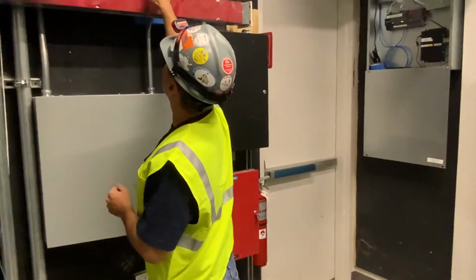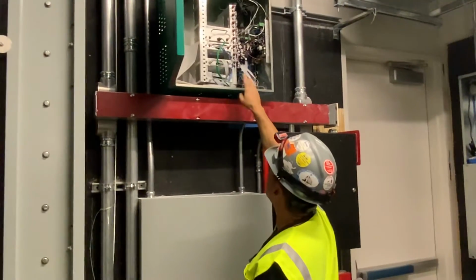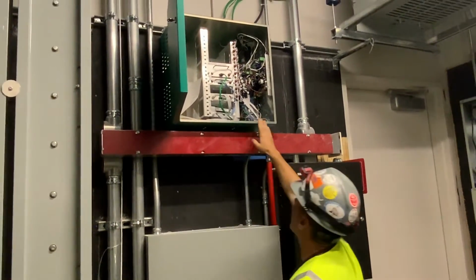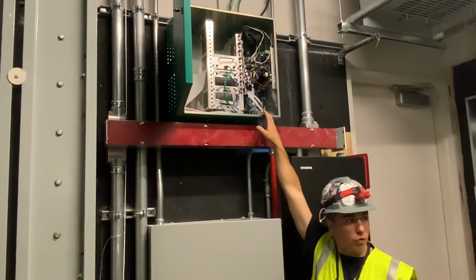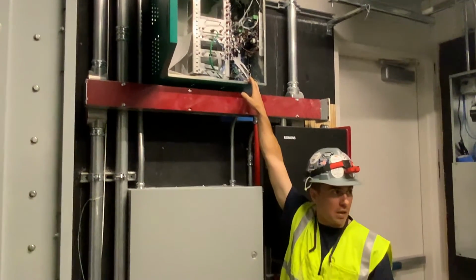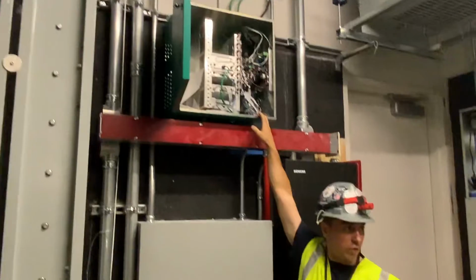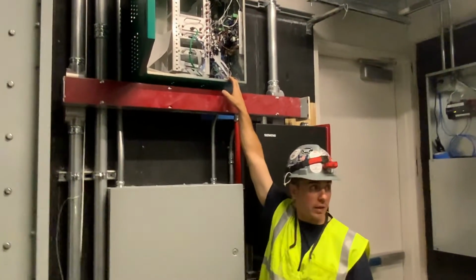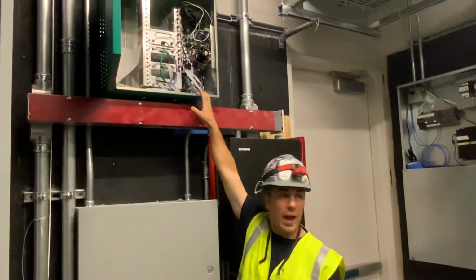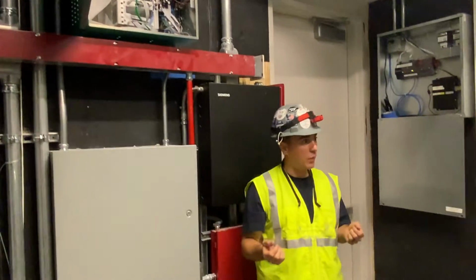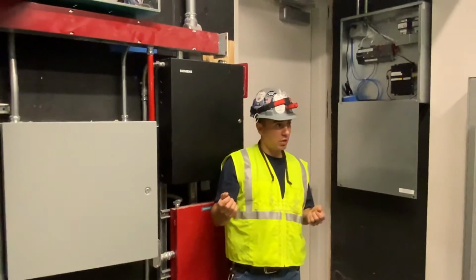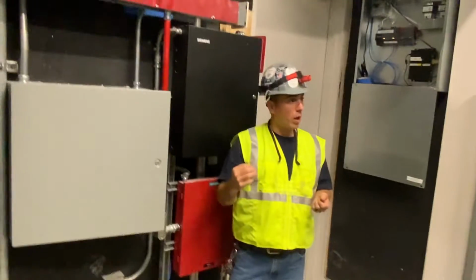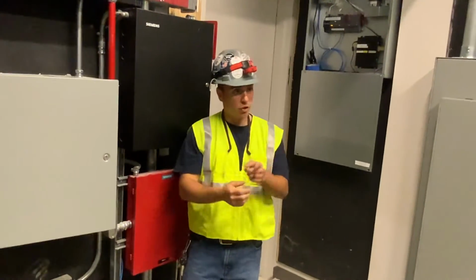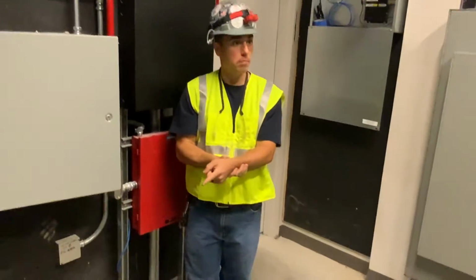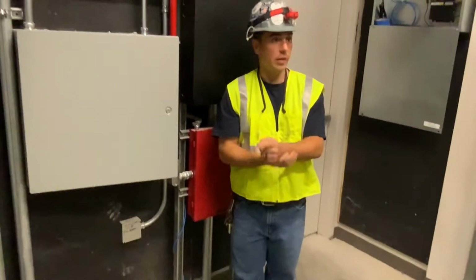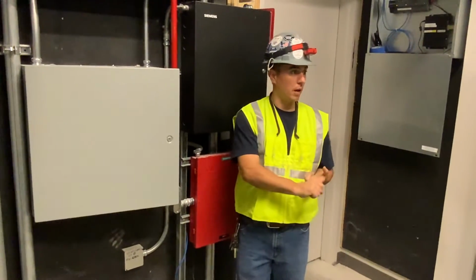Sensors that we have in here, we have CO2, carbon dioxide, we have dew point. So we have dew point, we can calculate relative humidity, but we don't have an actual relative humidity sensor. It's a dew point sensor and then we calculate a relative humidity. We have temperature sensors, so in that green tubing that we looked at downstairs, there's built-in wiring wrapped up in that, and then the sensor has an RTD sensor. So we are monitoring the temperature there, and that's how we get it between the dew point sensor and the temperature.